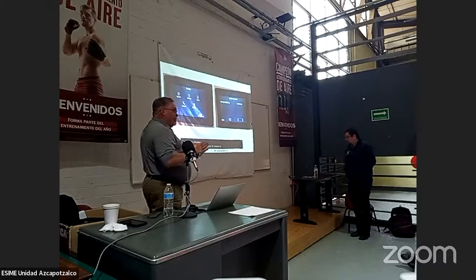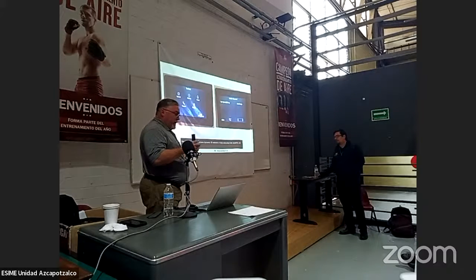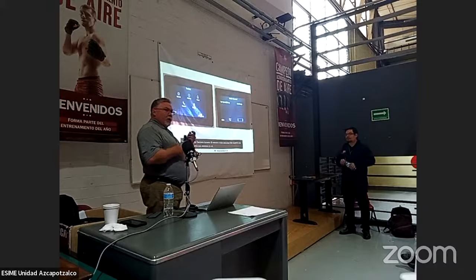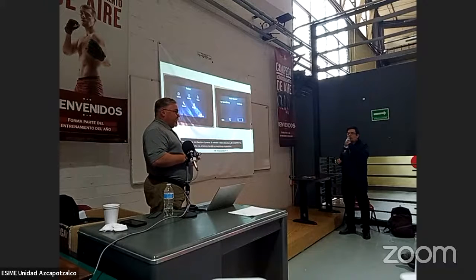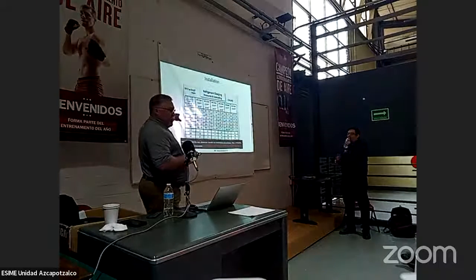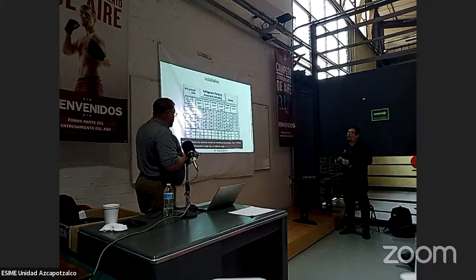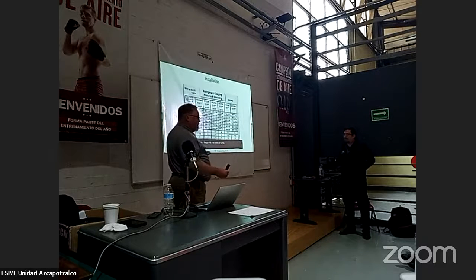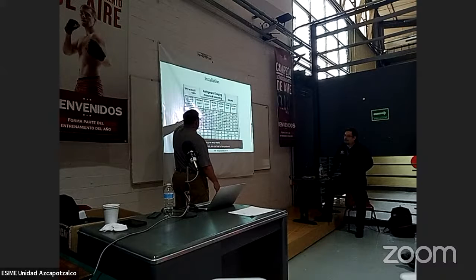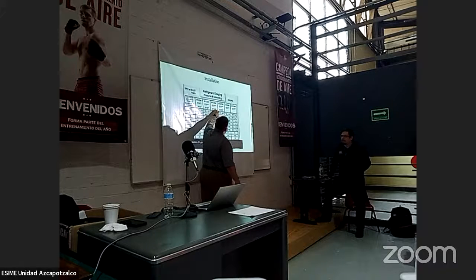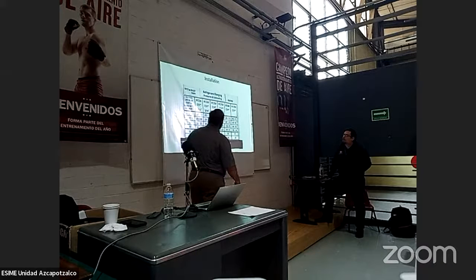Okay? Once you've done that, then you're going to have your gauges on. You're going to check your subcooling reading. And then you're going to go to your charging chart. Right? So this charging chart is very simple. You look at what temperature you are outside. Whatever your temperature is, wherever you fall in here, let's just use 95 degrees for outdoor air temp. And you're going to use that's RQ17. Let's jump to RQ23.